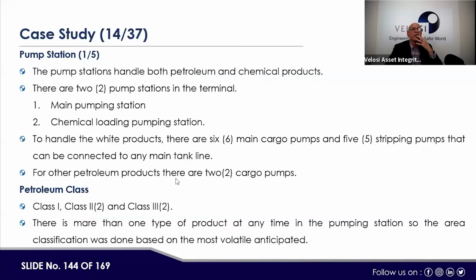Then the pump station. The pump station handles both petroleum and chemical products. There are two pump stations in the terminal: the main pumping station and the chemical loading pumping station. To handle the white product, there are 6 main cargo pumps and 5 stripping pumps that can be connected to any main tank line. For other petroleum products, there are 2 cargo pumps, petroleum class 1, class 2, and class 3. There is more than one type of product at any time in the pumping station, so the area classification was done based on the most volatile anticipated.